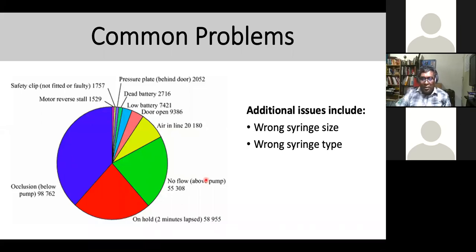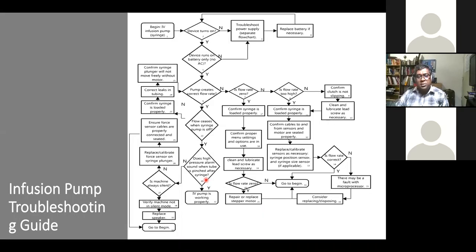We did attach a diagram on the infusion pump troubleshooting. The syringe pump and infusion pump troubleshooting methods are almost similar. When you start, you check whether the device can turn on or not. If it cannot turn on, you go to the lower part: is the device running on battery or not? So this is a flow chart that you're going to use to troubleshoot and make life easier. It's a guideline for you guys.